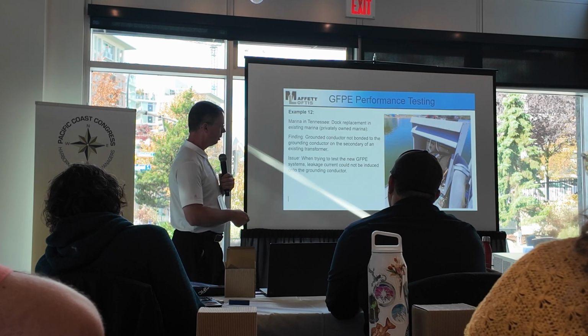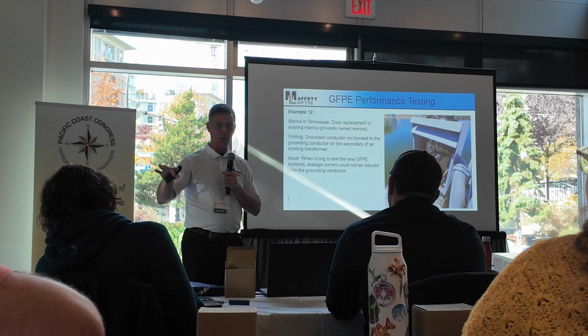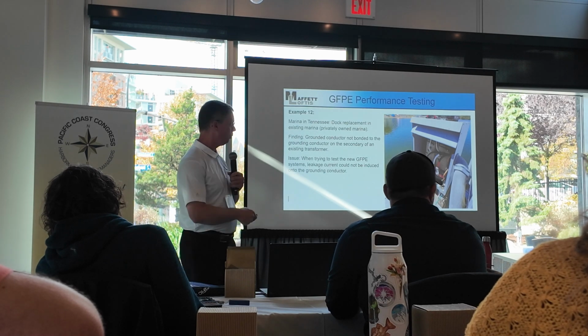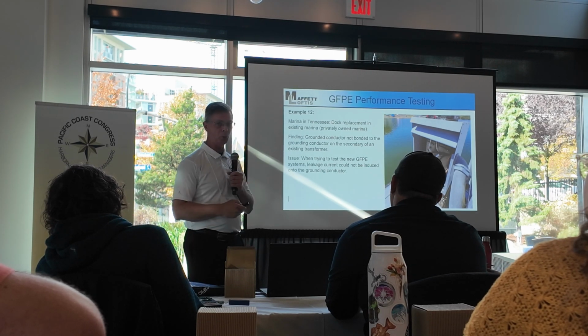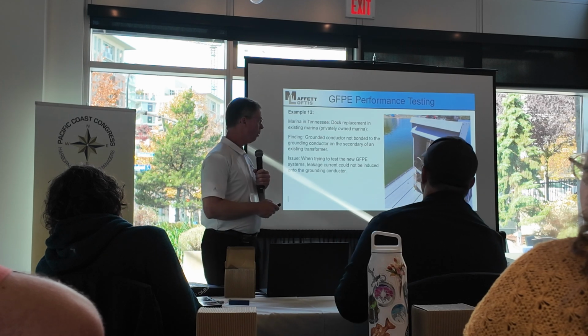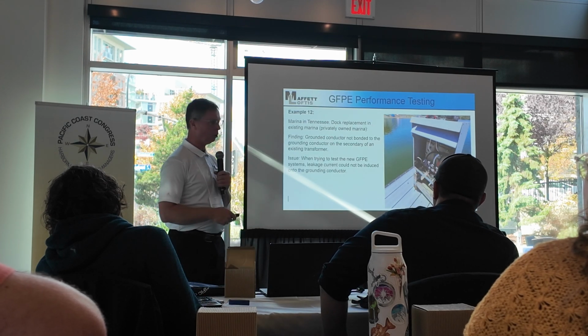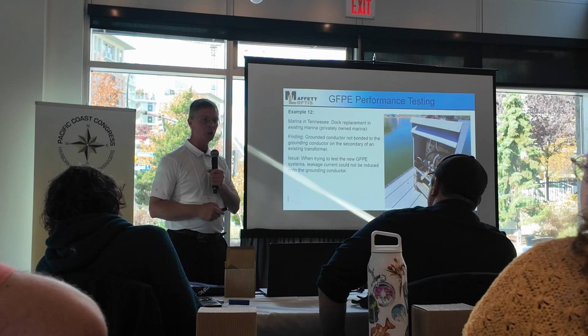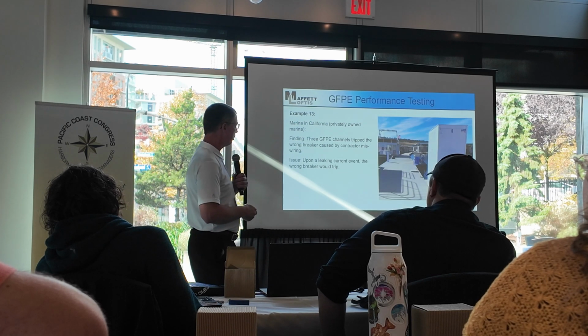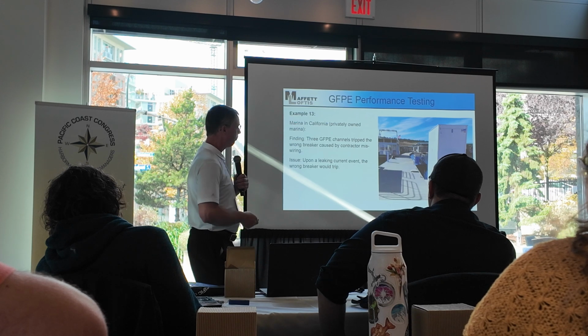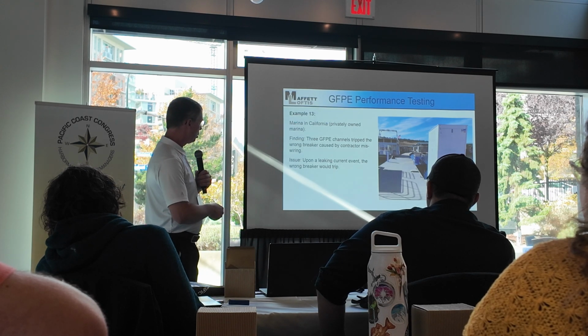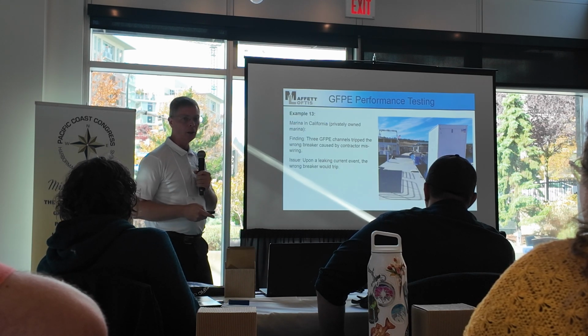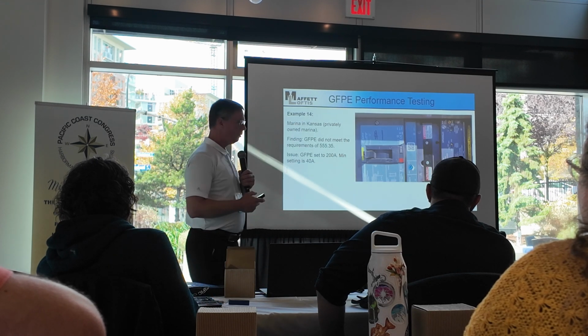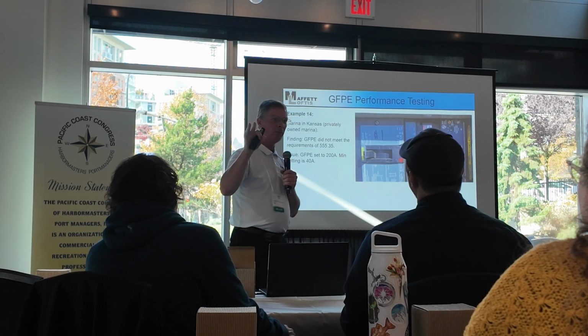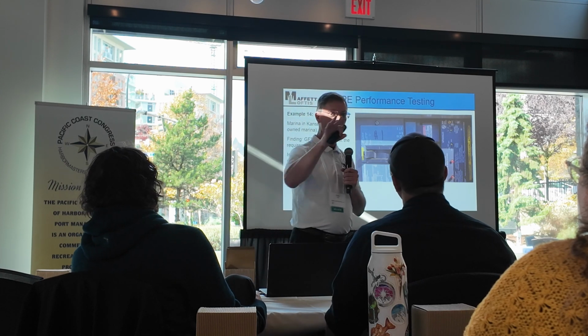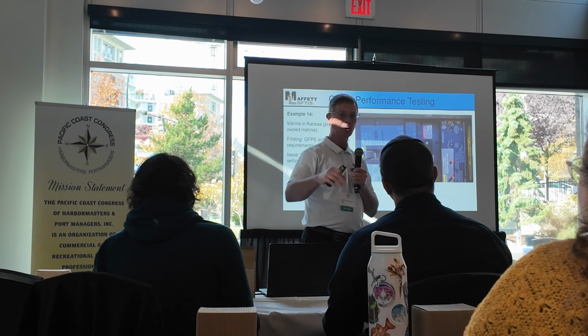The grounding system, this is a storm damaged dock. I redesigned the dock, had it wired, and we used an existing transformer to power it because the transformer was still good, but the grounding system wasn't attached to the neutral, so we didn't have any path to ground back. So that was a fairly major issue to find, and luckily we found it. Here's another one out in California that had a substation that would trip the wrong breaker again. So it's systems everywhere. And of course, what's the maximum limit on feeders and branch circuits? Milliamp wise, what is it, class? 100. 100 milliamps, right? Okay.